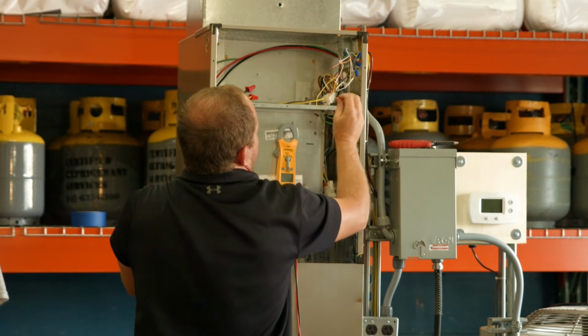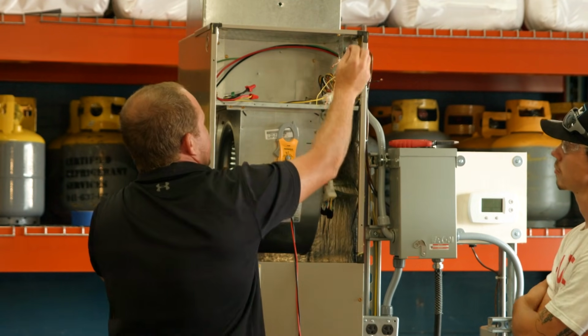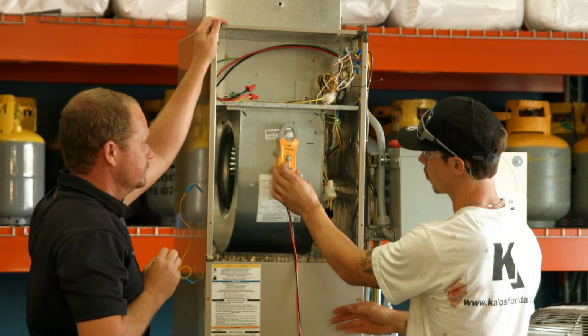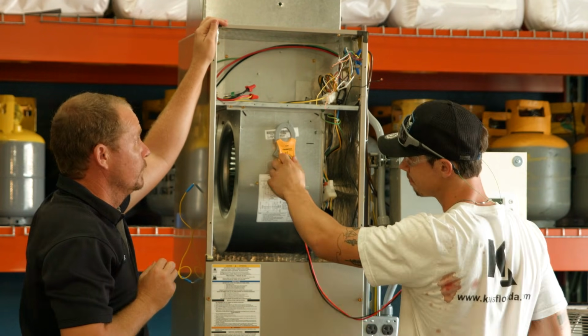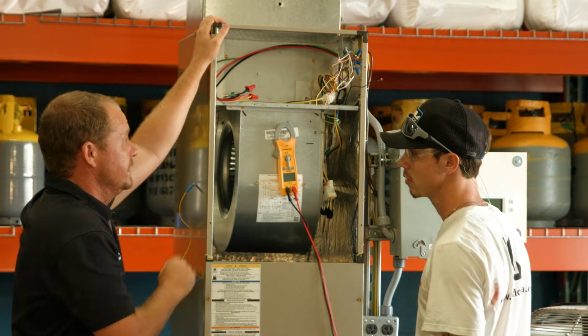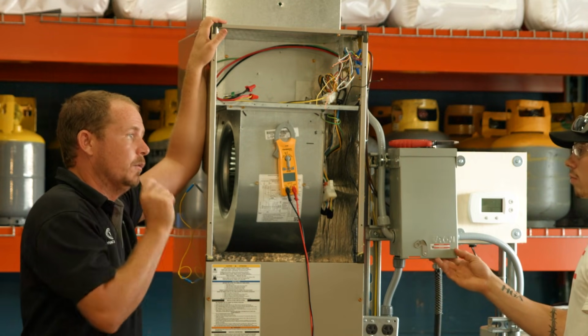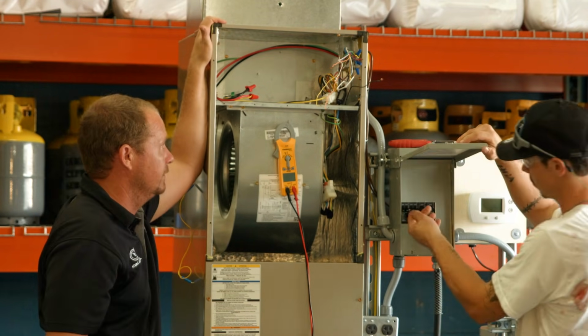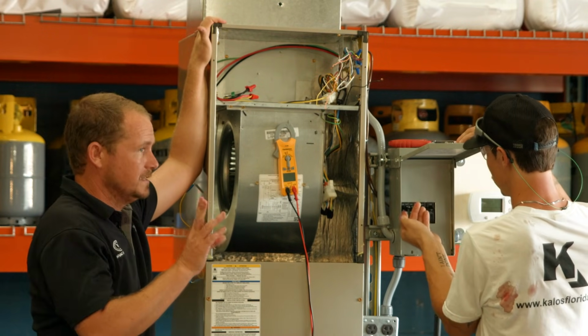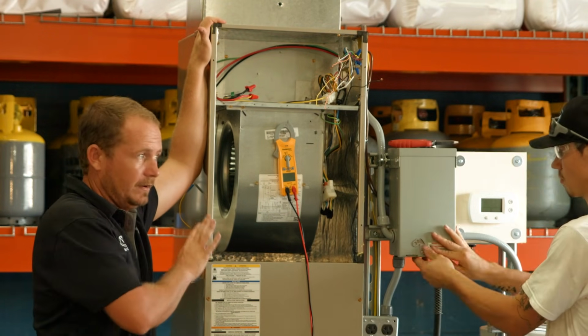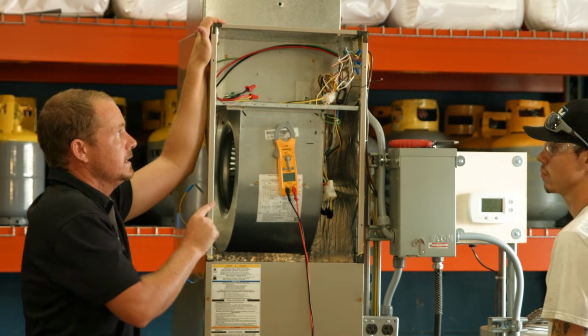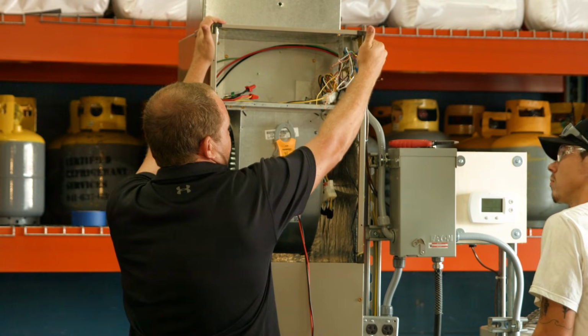So we're going to take each conductor now, and we're going to touch them individually to that. We're not going to use a meter at all, so this is a meterless test at this point. Now what we're doing, go ahead, power it on. So common's still connected, still connected to ground, everything's connected, the circuit's still intact. But now I have 24 volt power right here, right? Or at least I should.